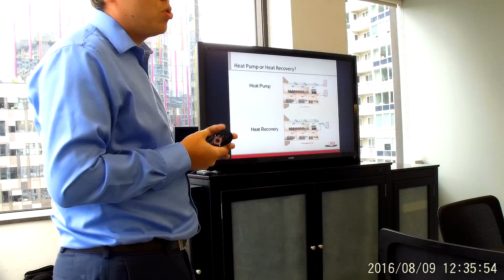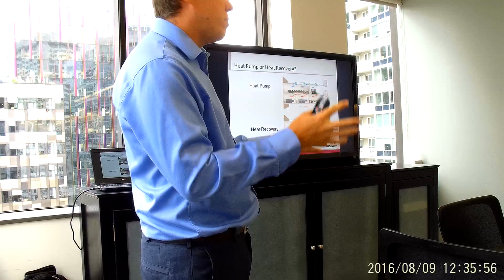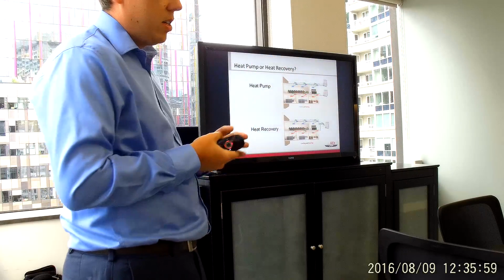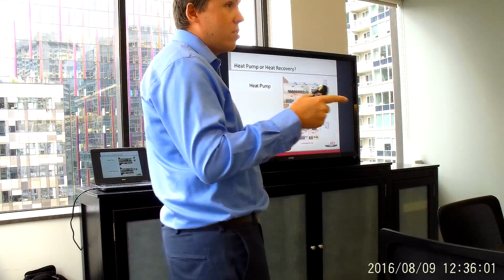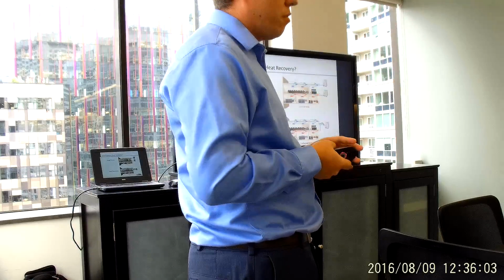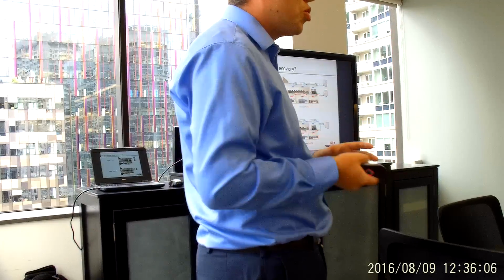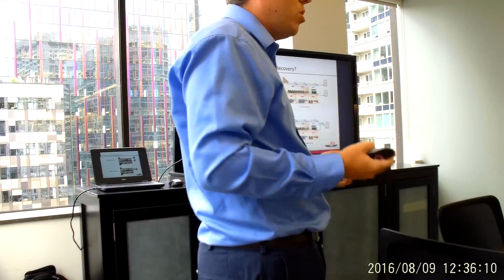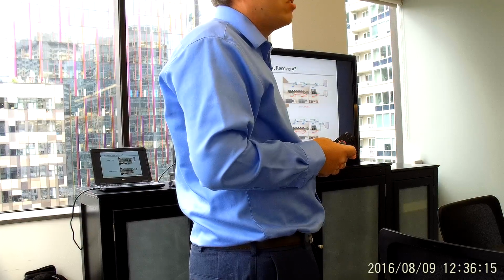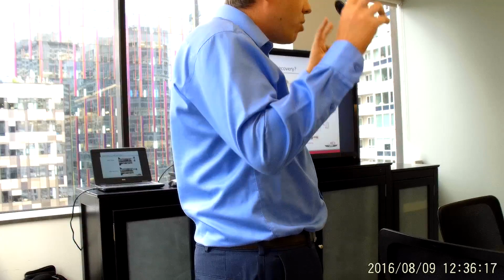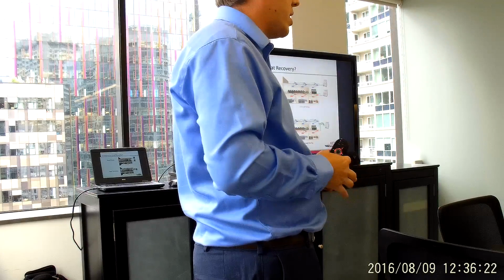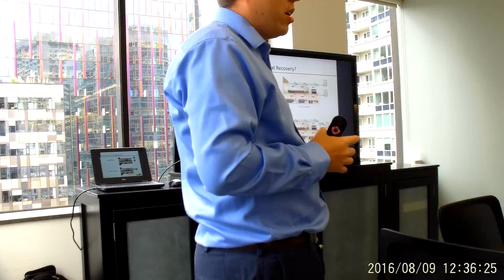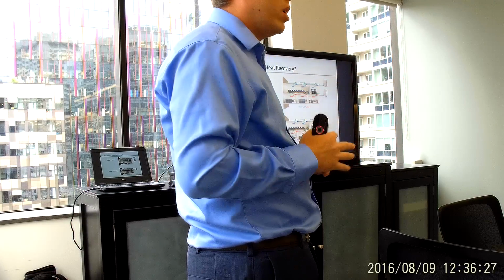I've personally run into issues by selling a heat pump system as a cheaper option to heat recovery, and I'll never do that again. As a consultant, I had to go back to that client two years after the fact. The developer would call me because I'm the engineer. They've dealt with the contractor, who says, well, that's the system you guys put in. Don't talk to me, I didn't design it. I had to go on site and speak to the developer. They'd read up on VRF, thought it's heating, cooling, full simultaneous. He forgot about the fact that I told him it's either or. And it's one thing to say I told you so.